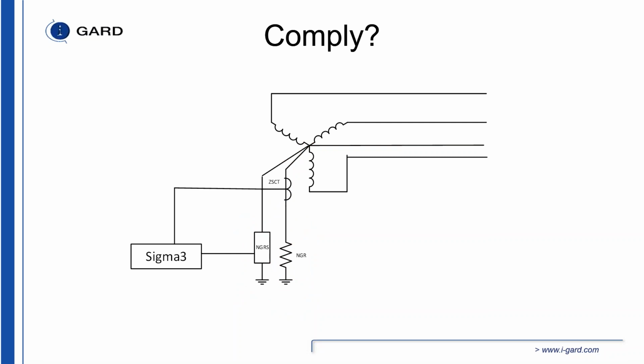So what we've done is we've had to have a second wire going to the X0 bushing of the transformer so that we can show continuity. So we're going to have a signal impressed upon the neutral. It's going to go up to the X0 bushing and back down here. So we can monitor the integrity of this line, but we have to have two conductors going to the X0 bushing of the transformer to monitor the state of that conductor, whether it's open or shorted.